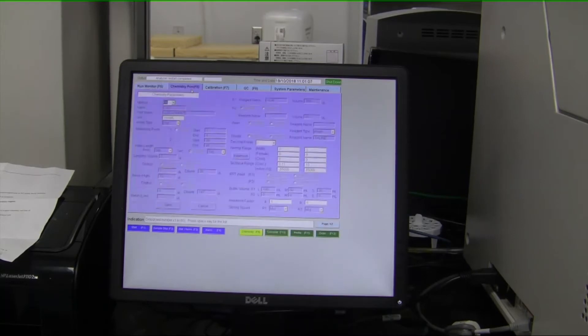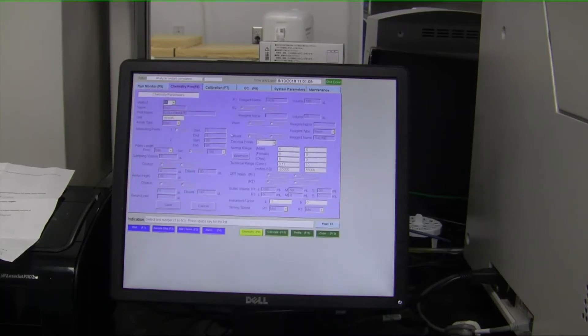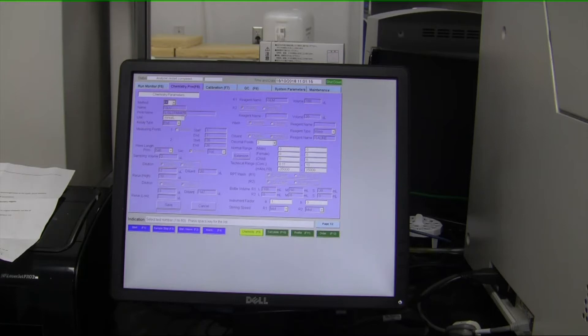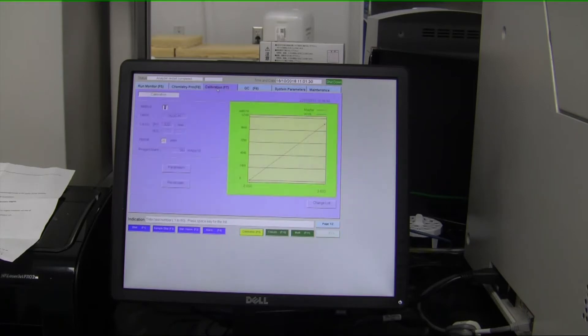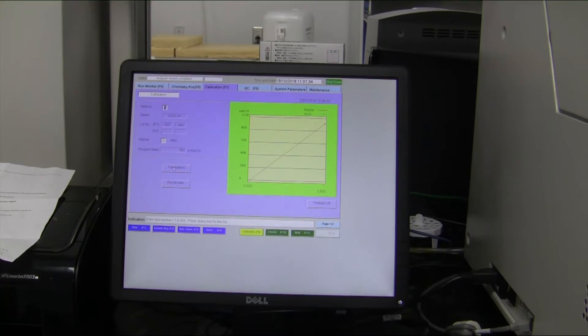If you wanted more advanced information about what the machine is doing in background, chemistry parameters will tell you all about each specific metabolite, what its measurement units are, how much sample and how much reagent is being put into the cuvette, and what specific optical frequency the measurement is being done at. But this is all things that are being done in the background of the instrument. Under calibration you'll have your calibration curves, and under parameters you're able to enter in your calibrator values.